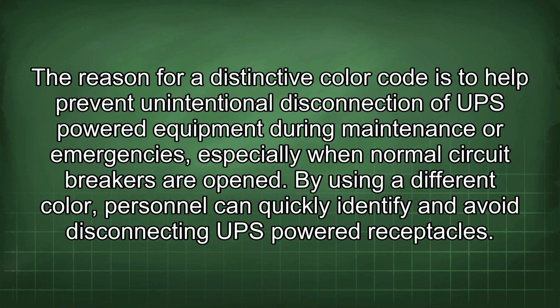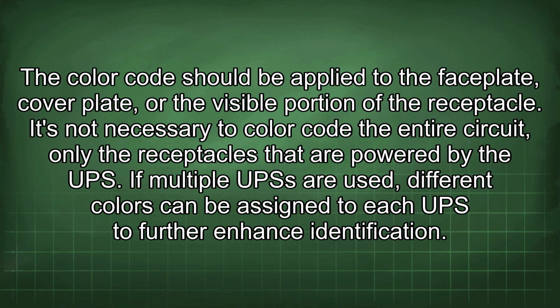The reason for a distinctive color code is to help prevent unintentional disconnection of UPS-powered equipment during maintenance or emergencies, especially when normal circuit breakers are opened. By using a different color, personnel can quickly identify and avoid disconnecting UPS-powered receptacles. The color code should be applied to the faceplate, cover plate, or the visible portion of the receptacle. It's not necessary to color code the entire circuit, only the receptacles that are powered by the UPS. If multiple UPS are used, different colors can be assigned to each UPS to further enhance identification.